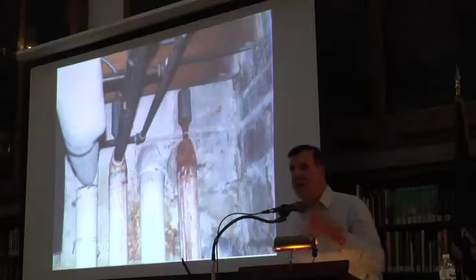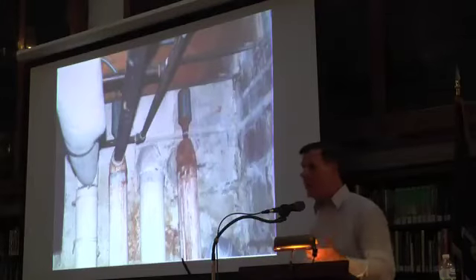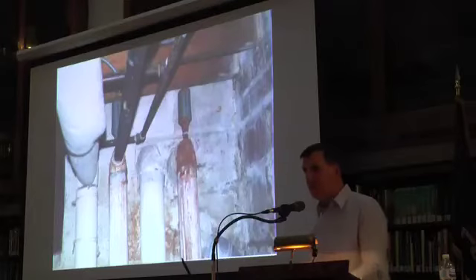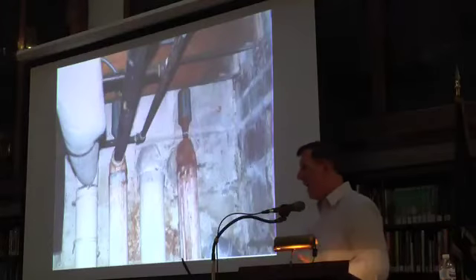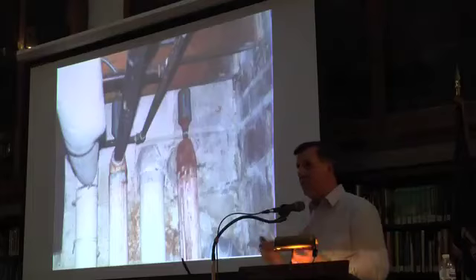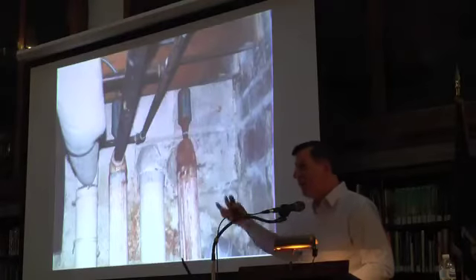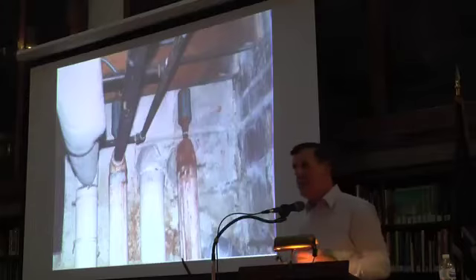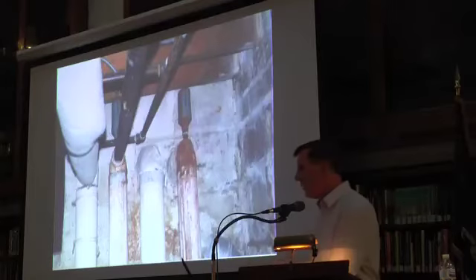Wander down the end of the line and you see, okay, there's the green air vents, and what's on the pipe there? That's what we call pipe vomit. This is what happens when the pipes can't take any more and it just spits all that crap, all that rust, out of its top, down onto the pipe, and as it's spitting all that rust, the rust gets into the little hole that's in the air vent that's supposed to vent the air and plugs it up. At this point, some knucklehead shows up and raises the steam pressure, thinking that that's going to get more heat out to the building.